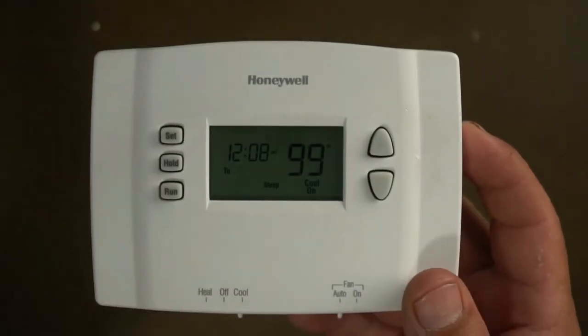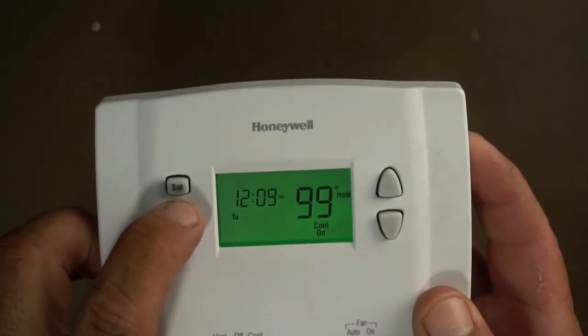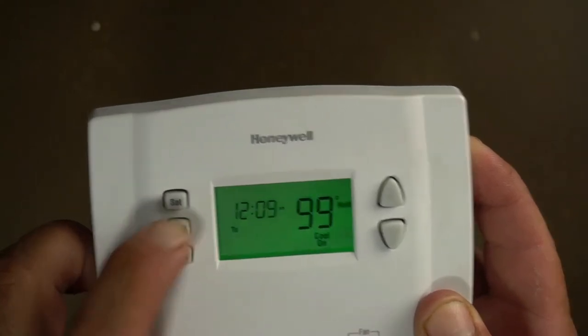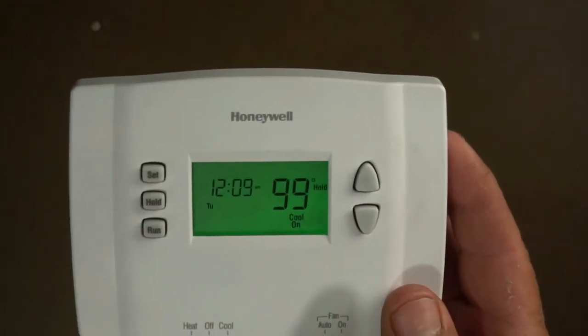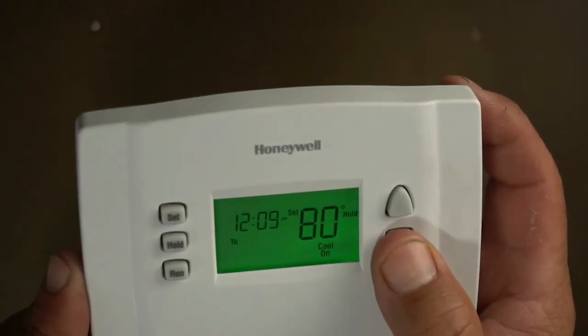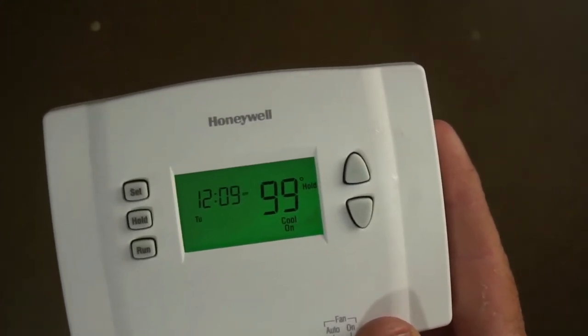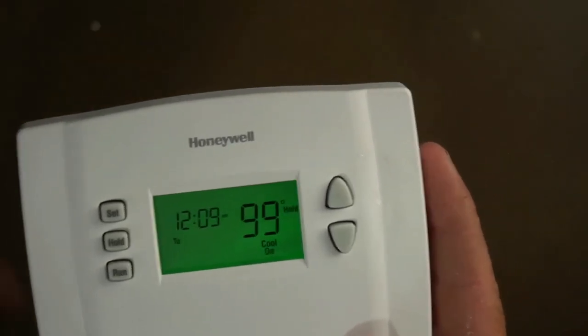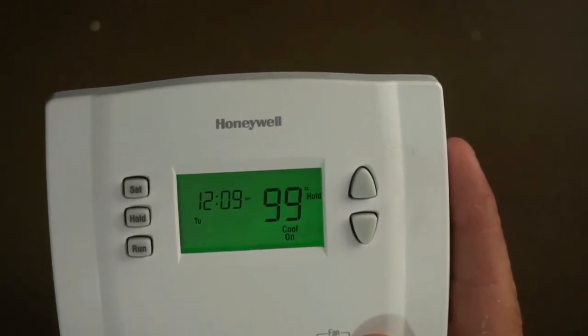If I just wanted to use this thermostat as a regular thermostat, all I've got to do is press the hold button for a few seconds. It's on this side. Once hold is on, let's say I set it at 75 — it's going to be turning on and off at 75. That's normal. It's just going to run as a normal thermostat. I have it set at 75, so it'll hit target and shut off normally. As long as it says 'hold' on this side, the thermostat is running normally. It's just going to shut off when it hits the target of 75.